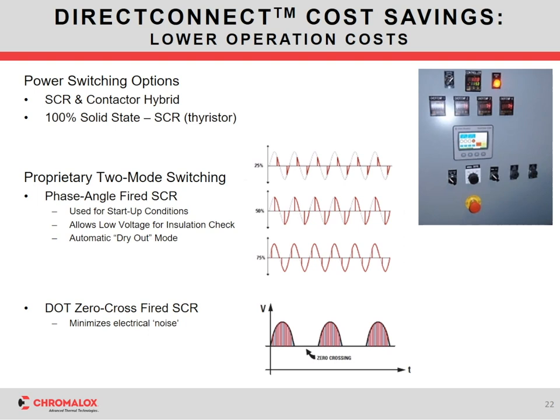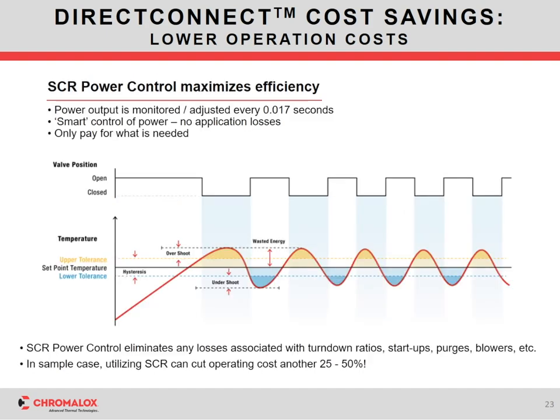And what that does is it chops the waves up only at the 0 point, so that there's no electrical noise generated by the system. But again, a DirectConnect system has both of these installed with every system, and it's able to automatically switch between the two. And that's really what the efficiency is in an electric heating system. And so what makes this really great for any process is essentially it's a smart power control. So you don't have to worry about any overage or underages in an application. You're only paying for the power that's converted to thermal energy.